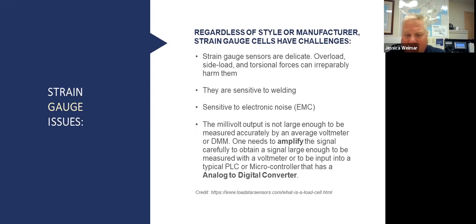In addition, strain gauge cells don't like to be side loaded. They don't like to see loads outside of the plane of the normal weight that they're trying to measure, nor do they like torsional or twisting forces, because any of those type of things can irreparably harm the actual strain gauge sensor unit. They're also sensitive to welding, because if you think about it, you've got the strain gauge unit adhered to the metallic beam, and if you're welding on a system that has one of these, the strain gauge itself can see the welding voltages and cause damage to the cell.